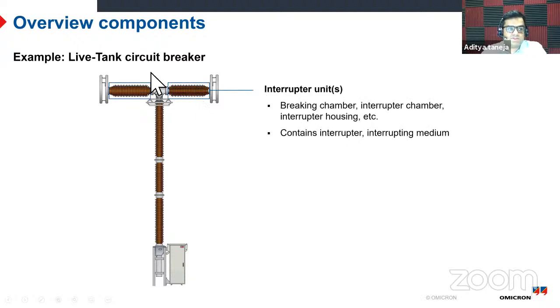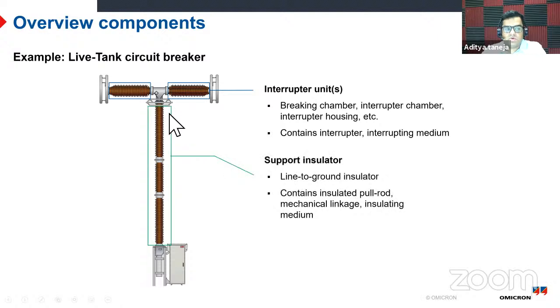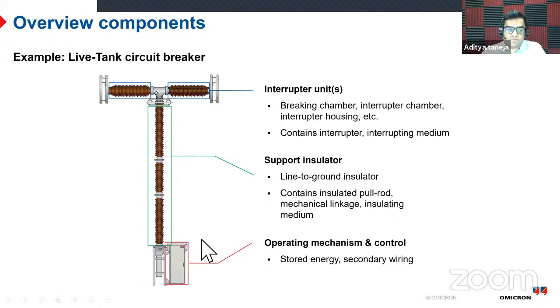So there is something which is interrupting the main currents and main voltage, which I call interrupter units. Whatever is inside that depends on the type. So first thing is the interrupter unit. Next is the support insulator, which basically supports the main structure and provides a housing for the linkage mechanism to move the breaker contacts. And then there is something which has the operating mechanism.